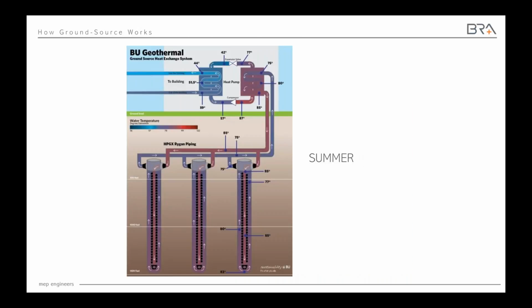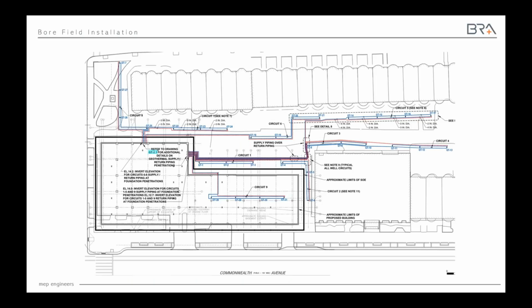So in summertime, we're gonna make that ground loop hot. We're gonna send heat into the ground and heat up the ground all summertime, and that's gonna allow us to use the ground as a cooling source. And then in the wintertime, on the next slide, we're gonna pull all that heat back out again and use it in the building. On the next slide, you can see the bore field layout. We have 31 boreholes, and 4 of them are actually under the footprint of the building, because all we had to work with was this skinny little alleyway in a corner park around the edges of the building.